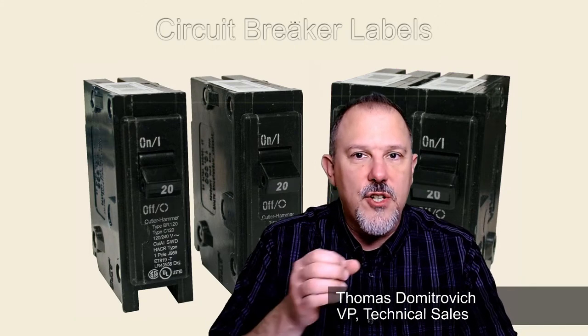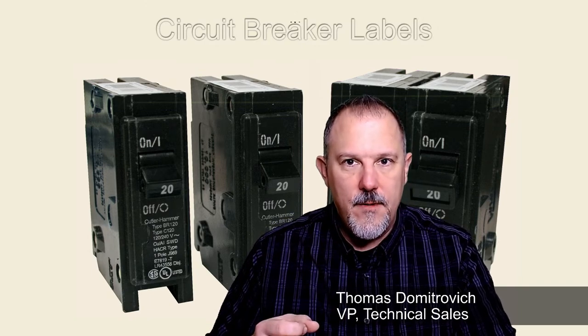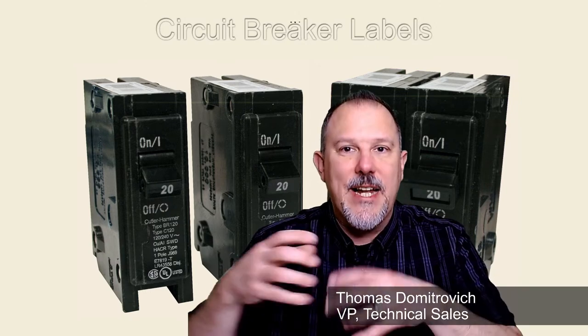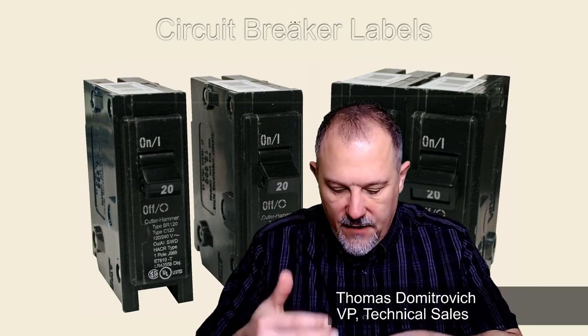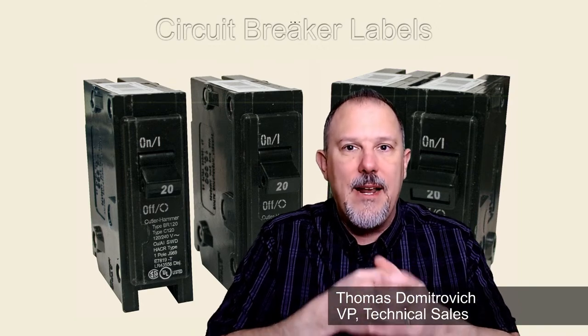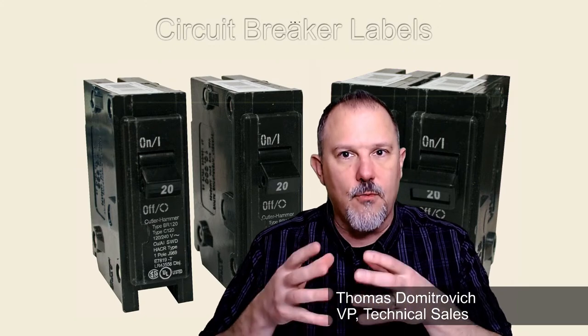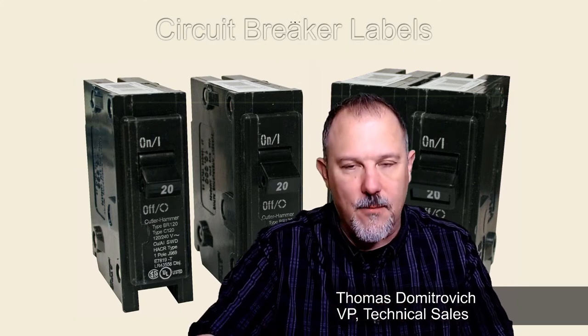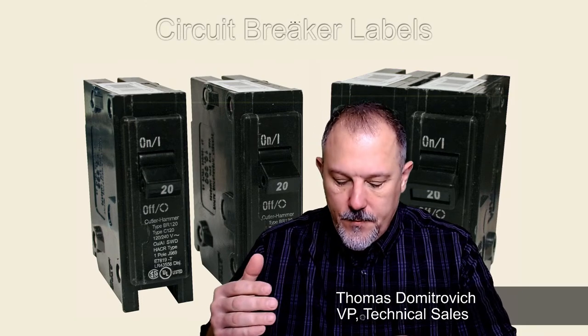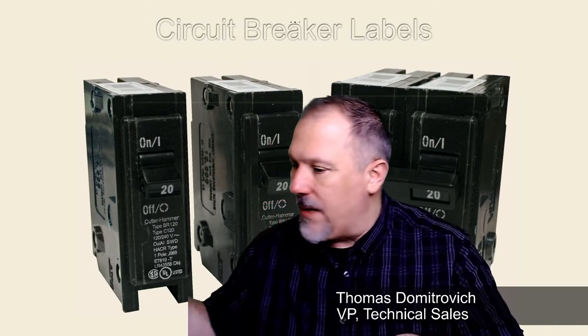A number one is a smaller amount of copper than a 1-aught. My breaker would need me to use a 1-aught conductor because I need that larger conductor for 150 amps. I need that copper on my lug to wick off that temperature. So it's about temperature rise and passing the temperature rise test in UL489. That's why these terminals are rated that way.